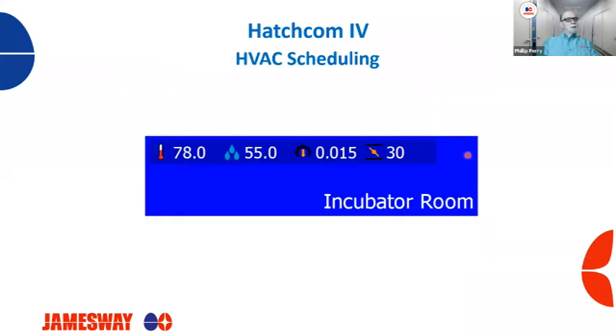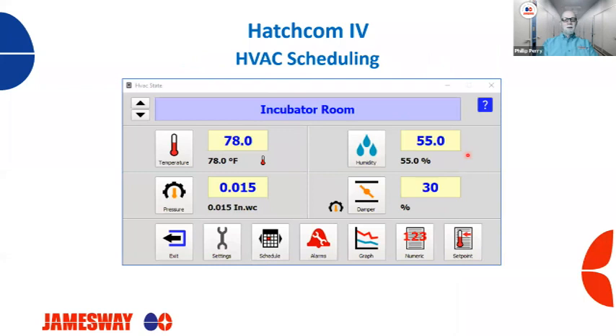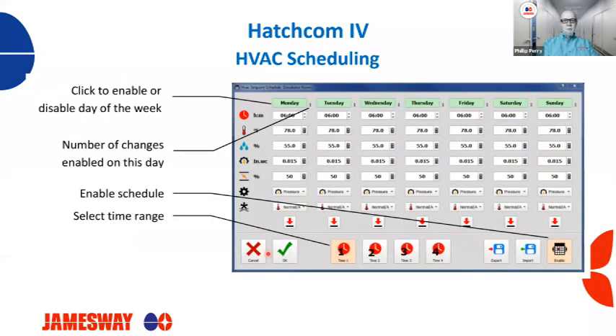Another cool function with the Hatchcom 4 is our HVAC scheduling. This function is used to set a schedule for a Guardian controlled room or plenum where Hatchcom automatically changes the set points or modes of operation. And it can do this up to 4 times a day. So from your layout, you would click on your incubator room, the schedule comes up, click on schedule, and then this window comes up. So this would give us all the different changes we can make, and you could reduce some energy costs.